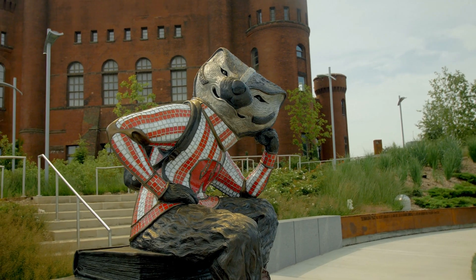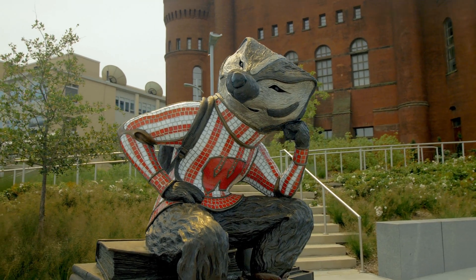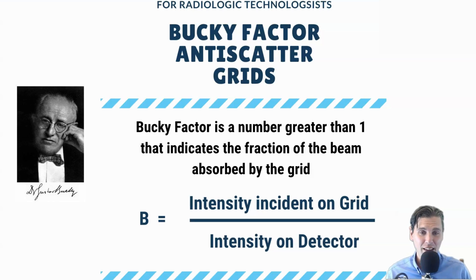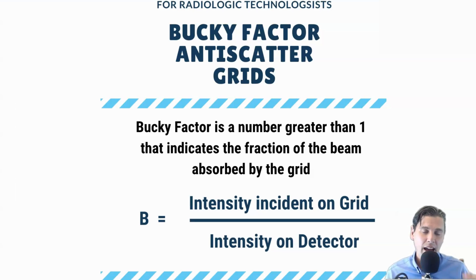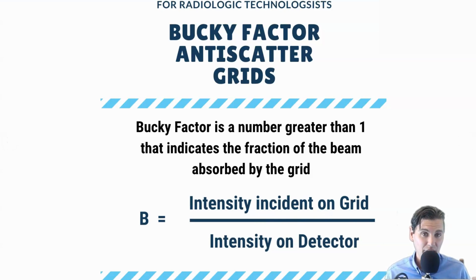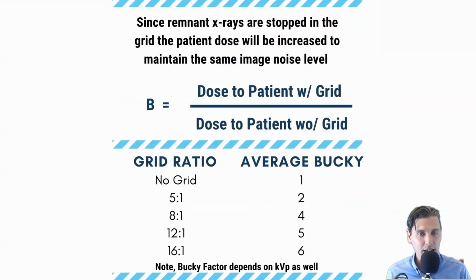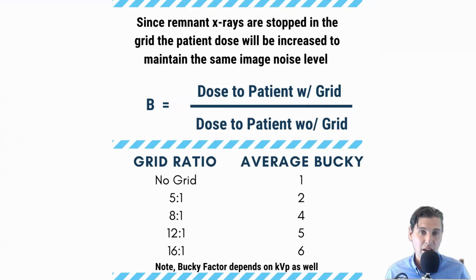That's where the Bucky Factor comes in — and it wasn't Bucky the Badger, but Bucky named after Gustav Bucky, who is the inventor of the x-ray scatter grids. This factor is a ratio, just like the contrast improvement factor was a ratio. It's the ratio of the incident intensity on the grid compared with the incident intensity on the detector. That number on top is higher because the grid filters out some x-ray intensity — so the Bucky Factor also represents how much we have to raise the patient dose when using a grid.